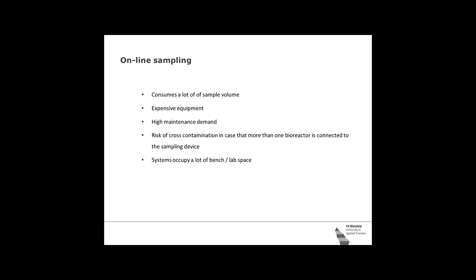Okay, so you need like 15 to 25 milliliters of sample volume per sampling. And that means if you sample like 10 times a day, you have 150 to 250 milliliters of sample volume to spend. So in a 2-liter bioreactor, that would take you 4 days and the bioreactor is empty. And that's the point, it consumes a lot of sample volume. It is expensive because you hook up by a sampling device also one or more analyzers dedicated to this one process. So it's not only the sampling device that is expensive, but also the analytics that you want to put behind, like an HPLC system, cell counter, whatever.